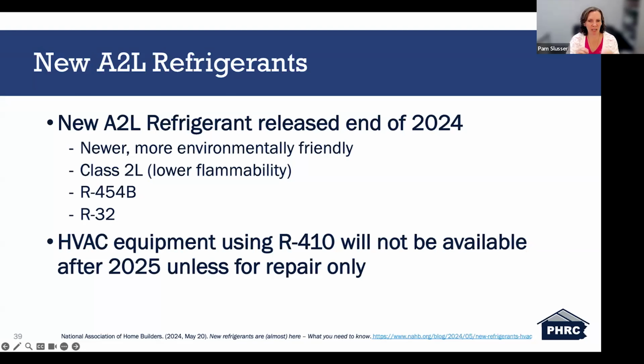So, some minor issues with this transitioning. The A2L might be slightly more flammable. There are going to be safety controls that will need to be installed, such as leak detection, which, if it detects a leak, will shut the equipment down. Also, an indoor fan will be installed to remove the refrigerant in case it leaks. This will require additional installation with new controls and wiring requirements. Indoor locations will become more critical and require thorough planning.